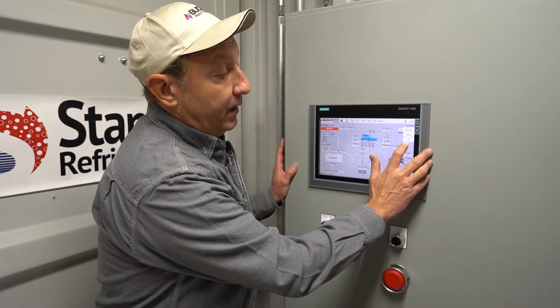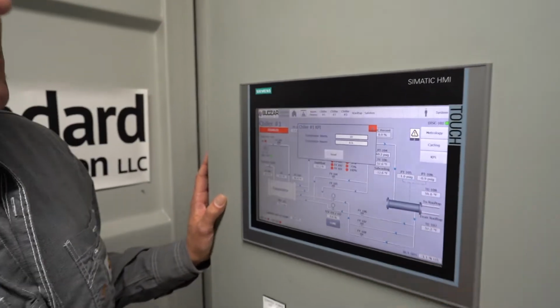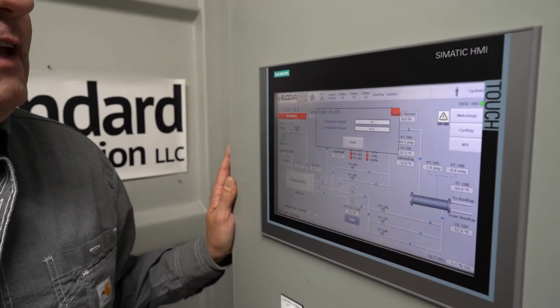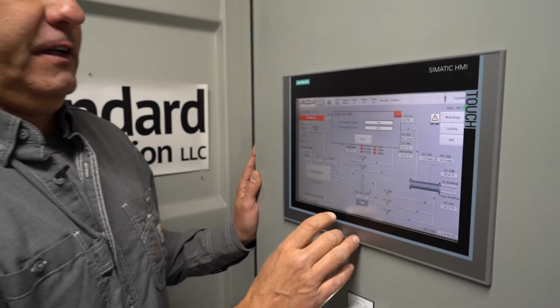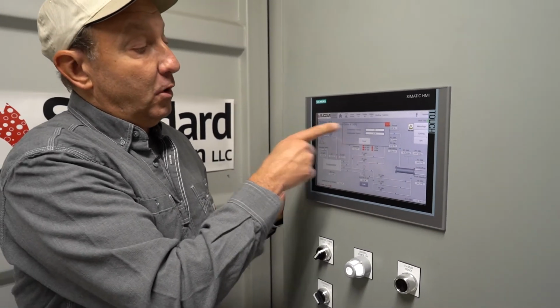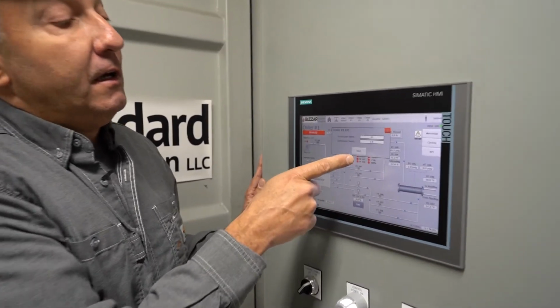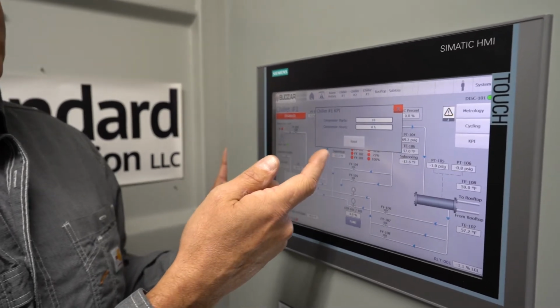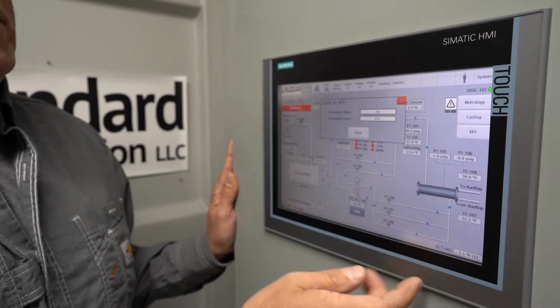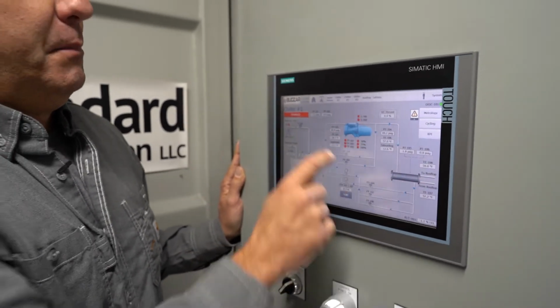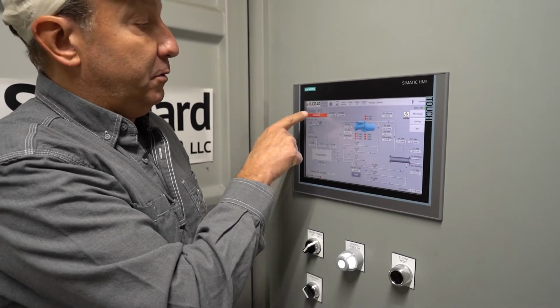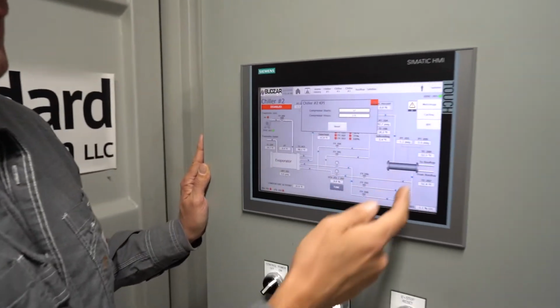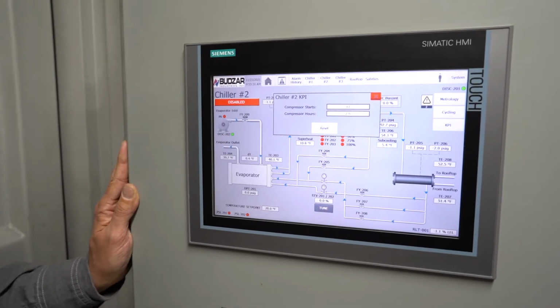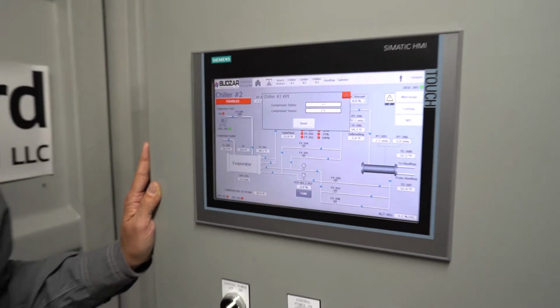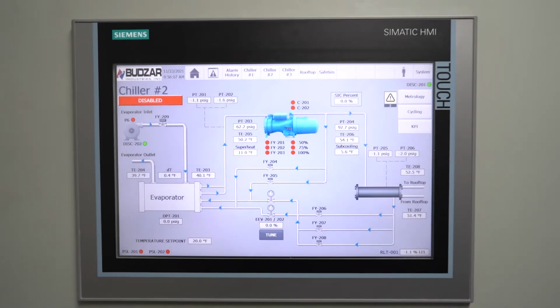This KPI button is the number of starts and compressor run hours for each circuit. For example, right now we're on chiller 1 KPI. Now this has been reset a couple times during our testing back at home for our factory acceptance test. But for example, I could go to chiller 2, we're now at chiller 2, and I press KPI, and it gives me the compressor starts and compressor run hours for that individual circuit.